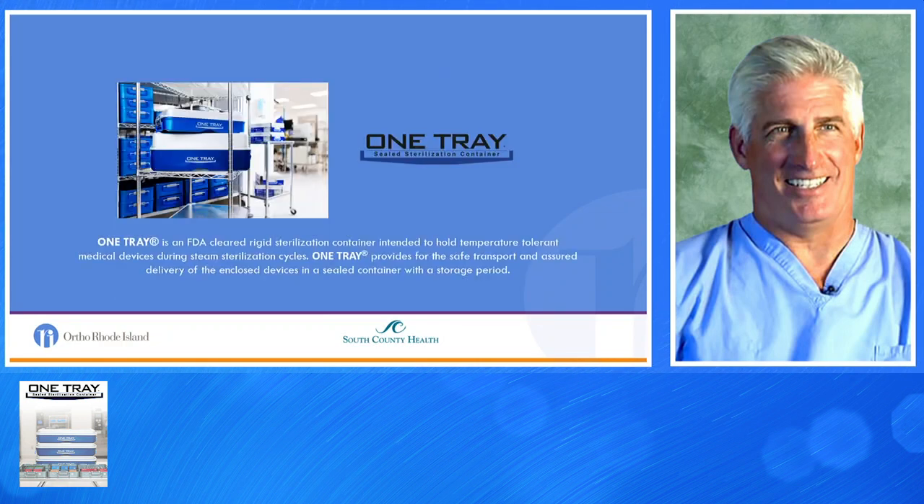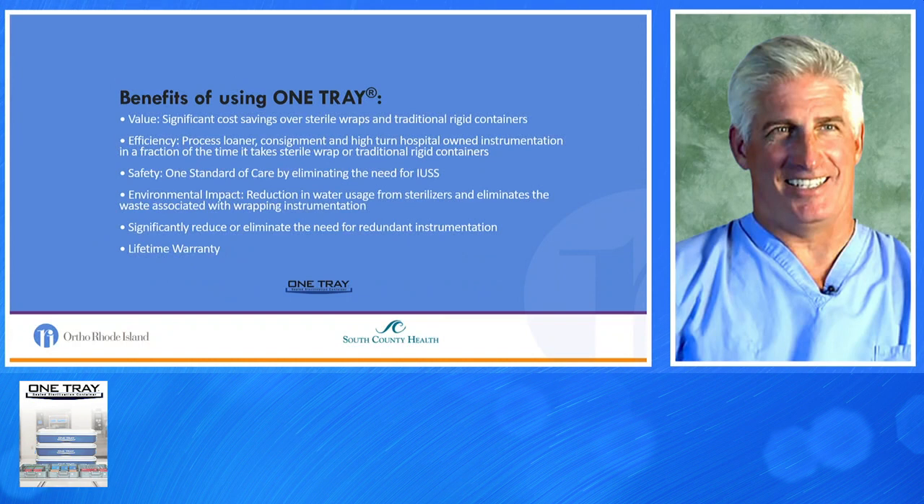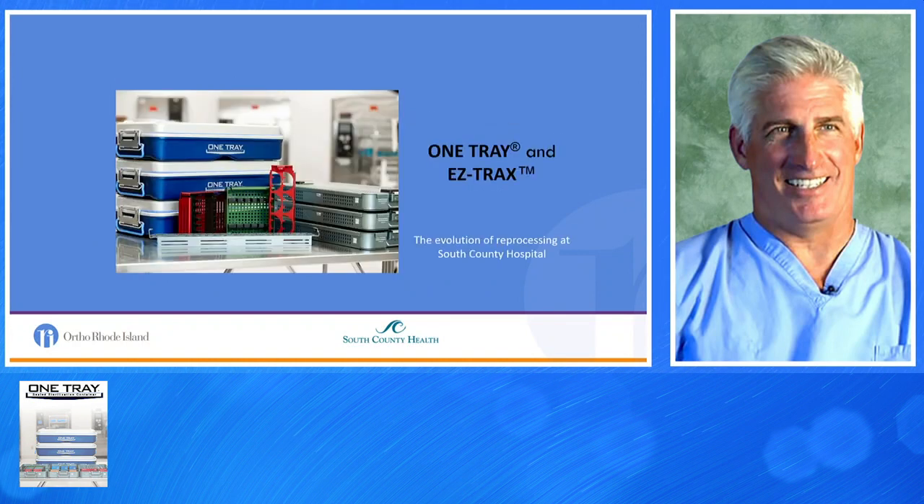One Tray is an FDA-cleared rigid sterilization container intended to hold temperature-tolerant medical devices during a steam sterilization cycle. It provides safe transport and assured delivery of enclosed devices in a sealed container with a storage period. The evolution of One Tray started about four years ago, and we most recently combined it with another addition called EZ-Trax.